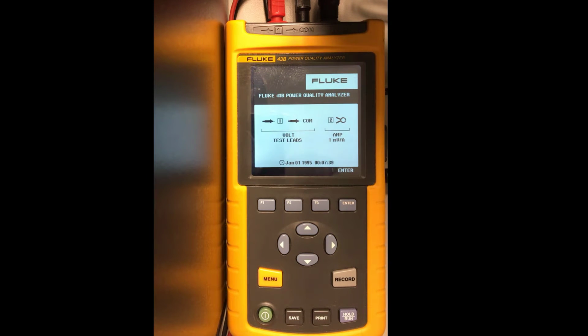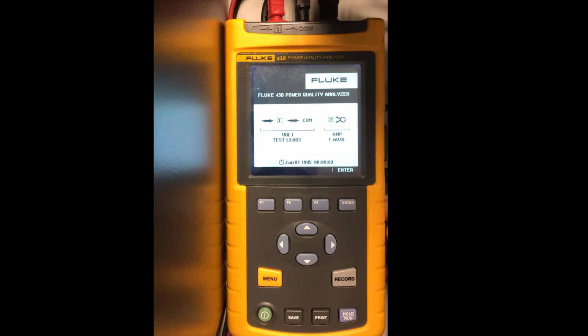Okay, so the next thing I'm going to do is turn it on with the power button. One thing to be aware of is you will not have reliable power to this device unless you make sure that the power connection on the right hand side right here is fully inserted and you're plugged into a power bar with power. If the power analyzer turns off on you consistently, it's because it's operating on its battery, and none of the batteries are very good in these analyzers anymore, so they won't last. So you've got to make sure you have AC power connected and that it's pushed in firmly to give you the power you need.